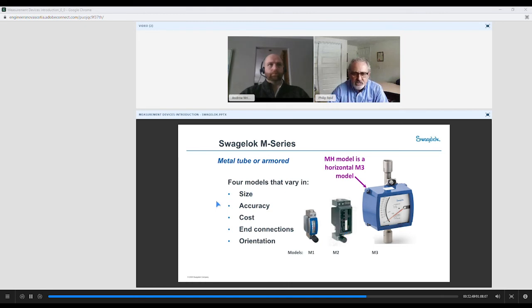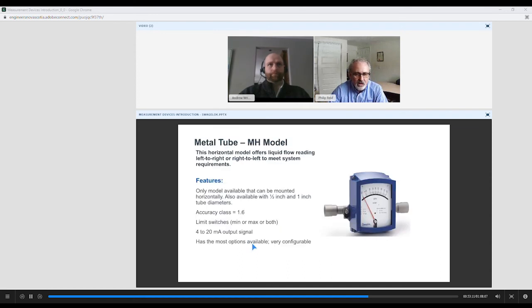So the 4 models vary in size and accuracy. As accuracy and size increases, so does cost, obviously. What type of end connections? Is it going into a pipe system? Is it welded, threaded, tube fitting, flanged? And then what the orientation of this flow meter will actually be in your system and how it has to be installed. So in these models, very high accuracy at 1.6.